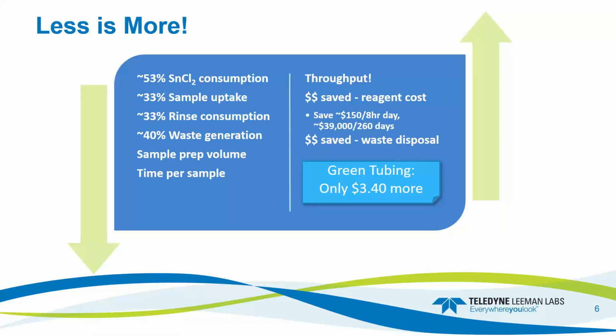So using the green chemistry pump tubing configuration means less is more. By reducing the internal diameter, and therefore the flow, stannous chloride consumption is reduced by 53%, sample and rinse uptake is reduced by 33%, and waste generation is down 40%. And because your sample uptake is less, this might allow you to scale down your sample prep procedure. And you can also reduce the amount of time per sample required for analysis with some method optimization.